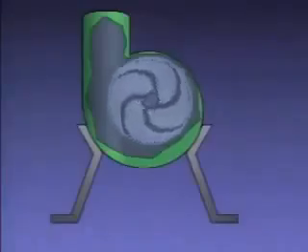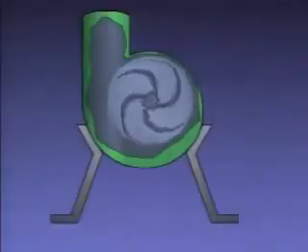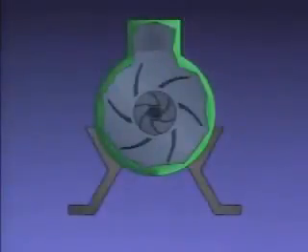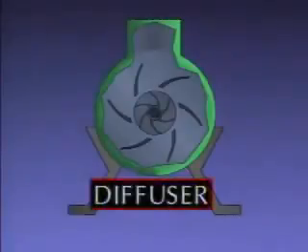Radial thrust is a type of thrust that tends to move a pump shaft perpendicular to its axis. In a pump with a volute, radial thrust is created by the difference in pressure across the volute. Some centrifugal pumps are equipped with a component that accomplishes the same speed-to-pressure conversion as a volute but minimizes radial thrust. It's called a diffuser.